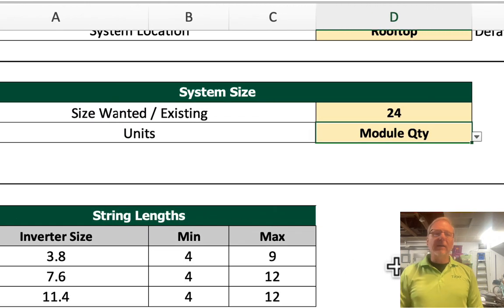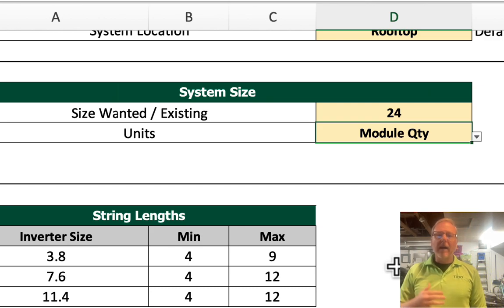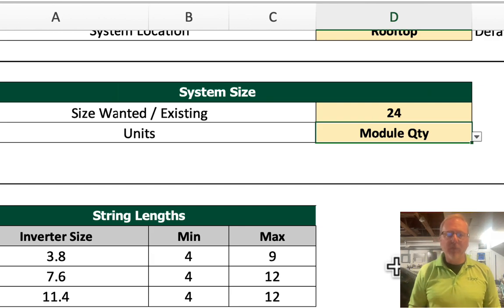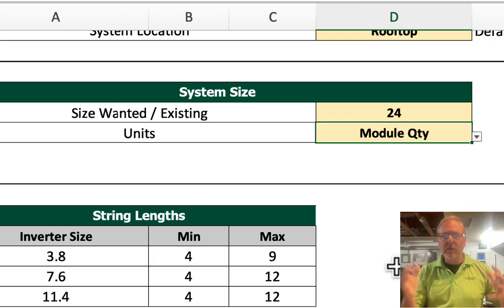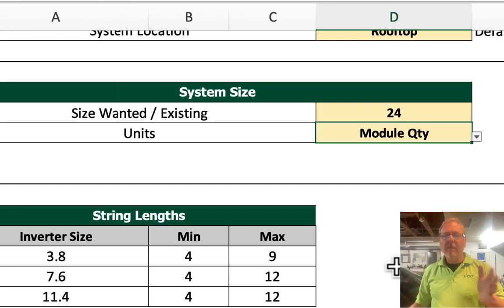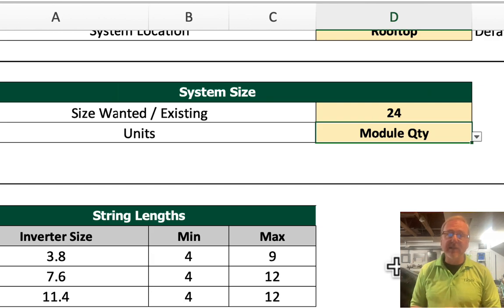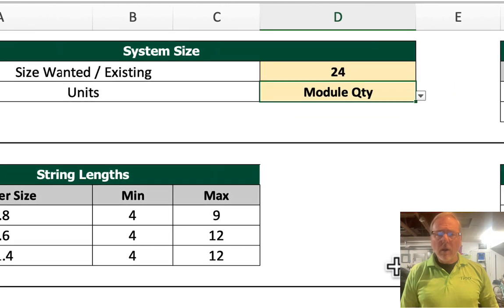When we come over here, the string lengths for the three Tigo inverters all start at four. For the 3.8 kilowatt, you can put nine of these modules in a string. For the 7.6 and the 11.4, you can put 12. That number is dictated by the upper end of the inverter — all of our inverter specs are in the background. You can't go more than this because you're either going to go outside the operating limits of the inverter or exceed 600 volts DC, which is not allowed by code.